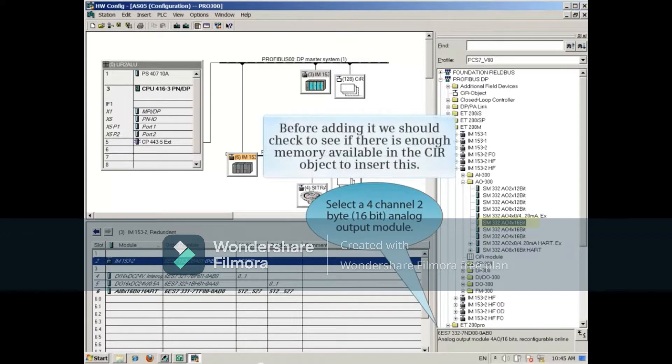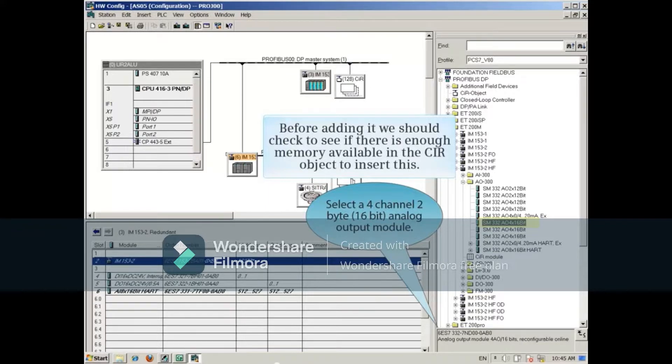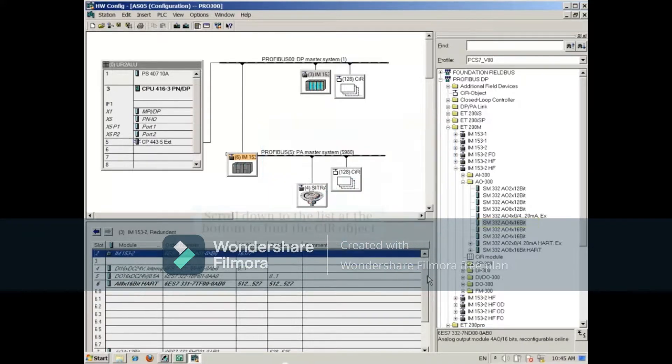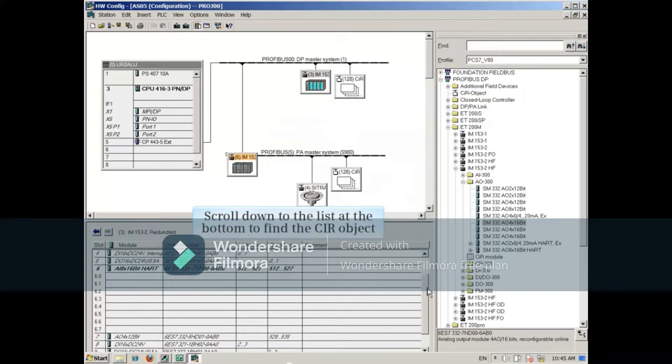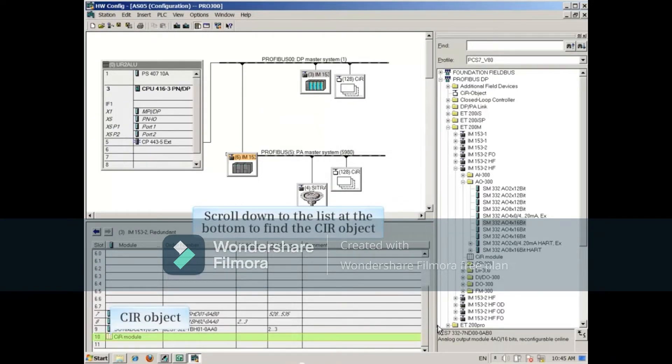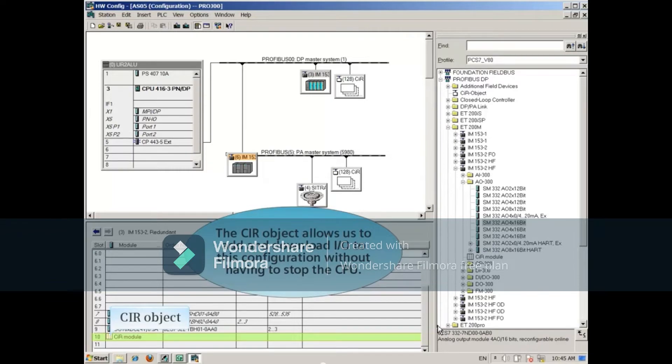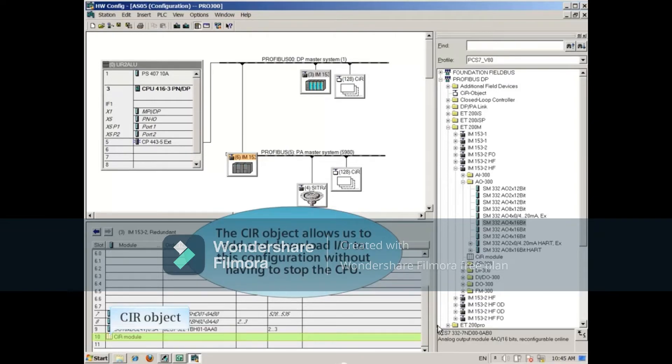Before adding it, we should check to see if there's enough memory available in the CIR object to insert this. Scroll down to the list at the bottom to show the CIR object. The CIR object allows us to add and download IO to this configuration without having to stop the CPU. If you're not using CIR, this object will not be here.